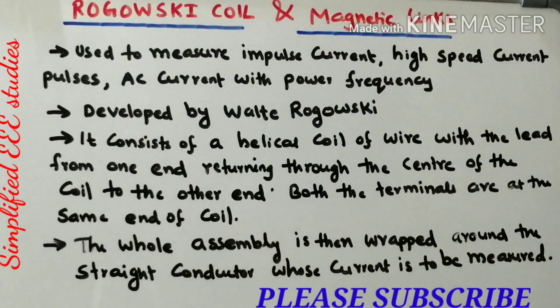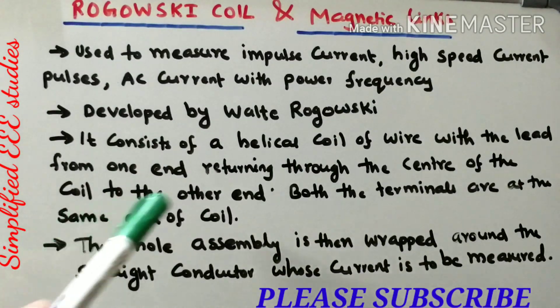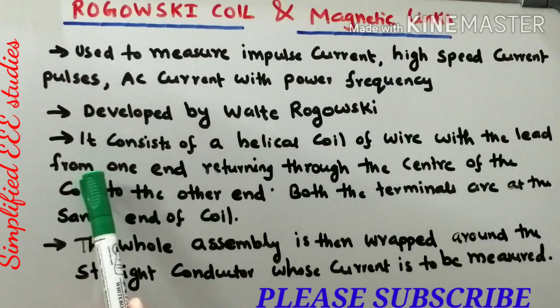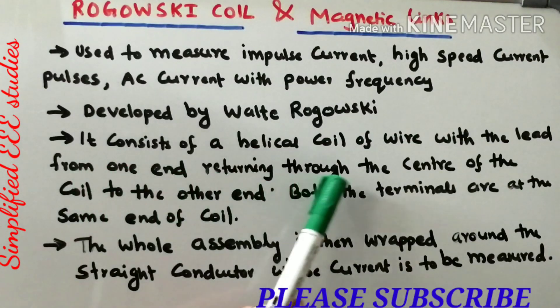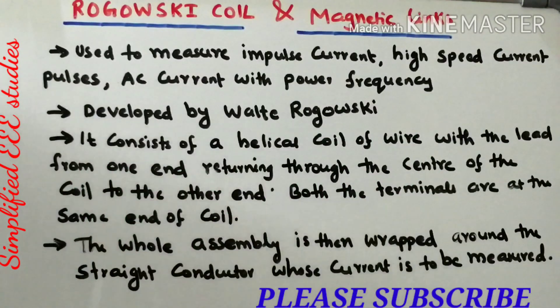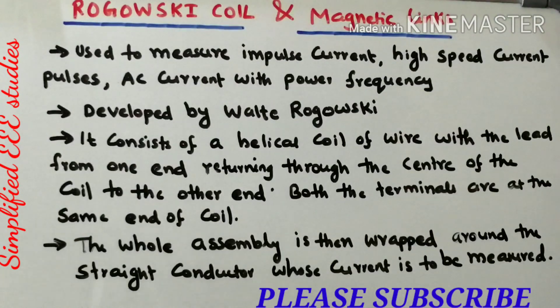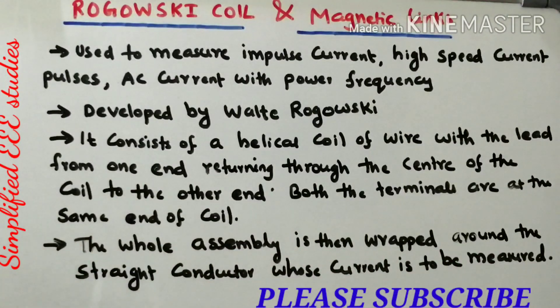It was developed by Walter Rogowski. It comprises a helical coil of wire with the lead from one end returning through the center of the coil to the other end, meaning both terminals are connected at the same end. The whole assembly is then wrapped around the straight conductor whose current is to be measured — giving it a toroidal shape.